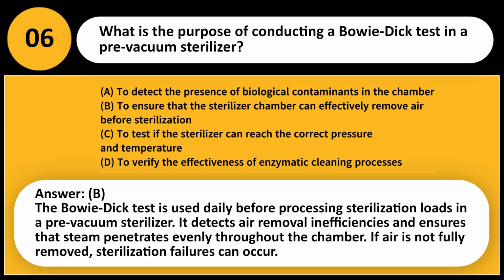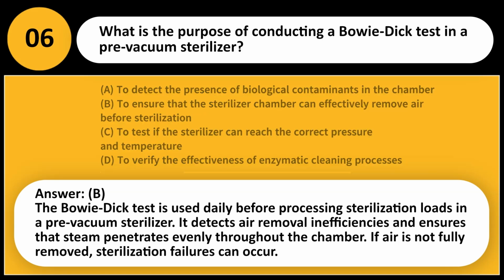Answer, B. The Bowie-Dick test is used daily before processing sterilization loads in a pre-vacuum sterilizer. It detects air removal inefficiencies and ensures that steam penetrates evenly throughout the chamber. If air is not fully removed, sterilization failures can occur.